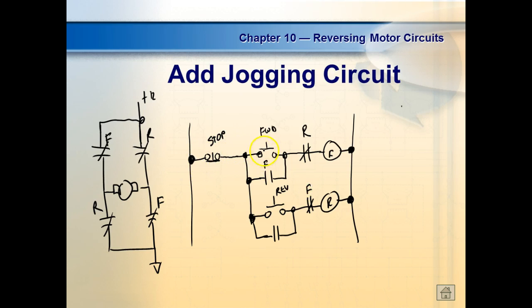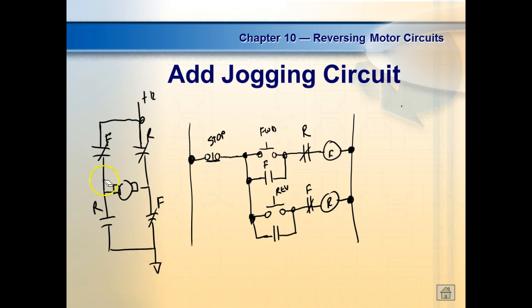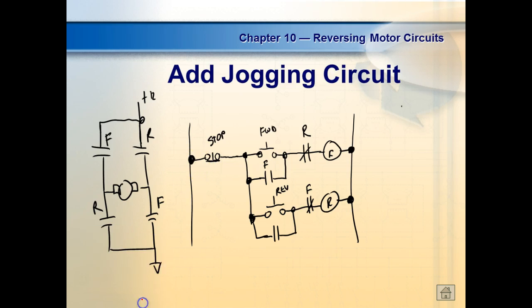So I come in here and I press forward, this contact opens, right? You understand? We come over here. So what would happen is, I hit the forward, it comes in, right? You understand? So here comes the power. Touch it, comes in, flies over there, hits forward, seals itself in, right? You see that? But what's going to happen to this contact? It's going to open up. So now I'm going forward, and the thing's running this direction. Well, I come over here and hit this reverse. That's going to let the power go to right there, but then it's going to stop. It can't get over to the coil, right? You understand? So this is what we call electrical interlocks.